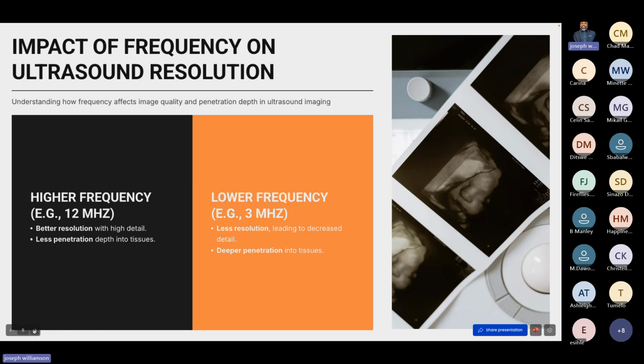So if I have a transducer, let's use some common sense here. If I have a transducer that only has 1 bend, it's going to be able to reach a lot further than a transducer that has 16 bends in it. The 16 bends are the frequency. The higher the frequency, the more bends I put into it, the less the wavelength. The wavelength is the reach. So if I'm imaging someone, as Chad said, that's 226 kg, I don't even want to look at anything over 3 megahertz because I know it's never going to penetrate that. However, if I'm imaging something superficial, like a breast or a thyroid or scrotum, and I try to use a low frequency, it'll blast right past the thing and I will never see it.